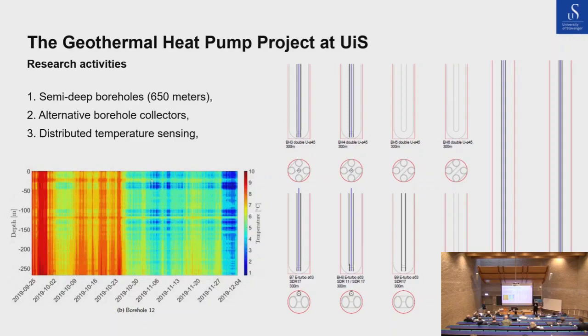There's been a lot of mention of the thermal gradient. When you go down in the borehole at some level, you actually heat the brine within the collector more, and then you send it back up, and it gets colder, and you begin to lose heat to the surroundings. So it's a sort of short circuit of the heat exchanger process. So the plan was to have one with standard thickness and another with a thicker wall on one of the pipes to sort of try to insulate and to measure that type of heat exchanger efficiency.